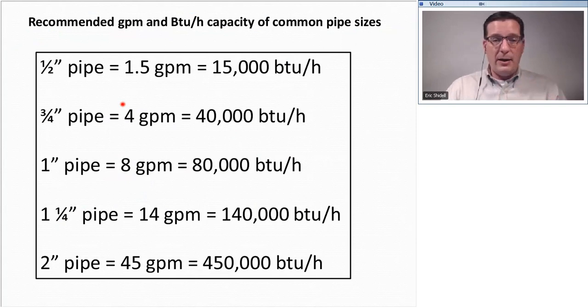One-inch, good for up to 80,000. Inch and a quarter, up to 140. Two-inch, up to 450. And these are the GPMs that are recommended for hydronic heating. If you're a plumber, you know that 3/4 inch pipe can handle a heck of a lot more than 4 GPM. But on hydronic heating, we want slow, quiet water flows, and that's why these GPM rates are so low.